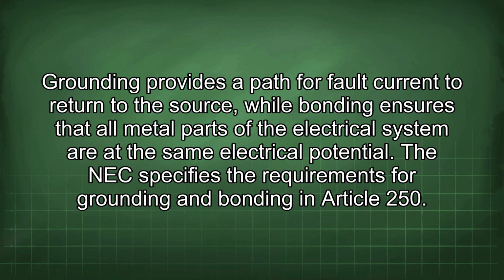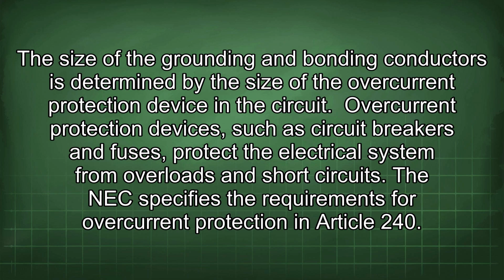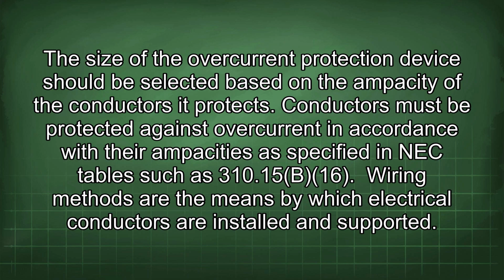The NEC specifies the requirements for grounding and bonding in Article 250. The size of the grounding and bonding conductors is determined by the size of the overcurrent protection device in the circuits. Overcurrent protection devices, such as circuit breakers and fuses, protect the electrical system from overloads and short circuits. The NEC specifies the requirements for overcurrent protection in Article 240. The size of the overcurrent protection device should be selected based on the ampacity of the conductors it protects. Conductors must be protected against overcurrent in accordance with their ampacities as specified in NEC tables such as 310.15(B)(16).